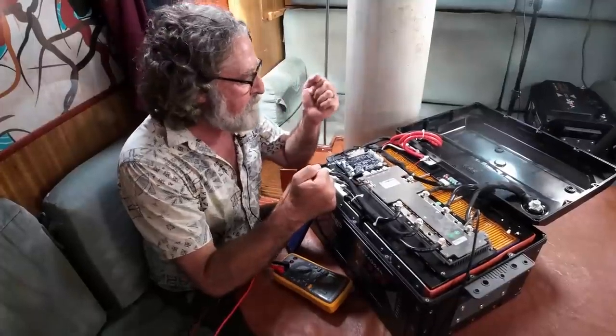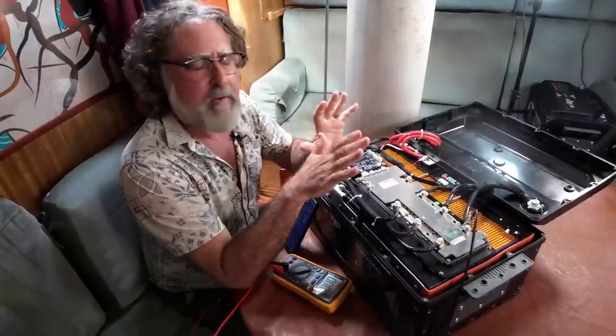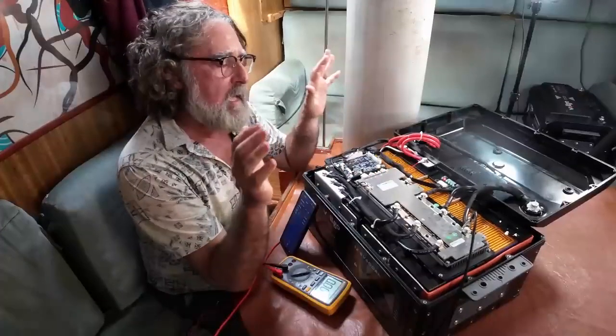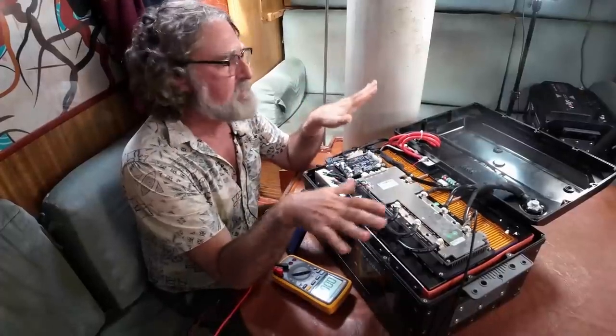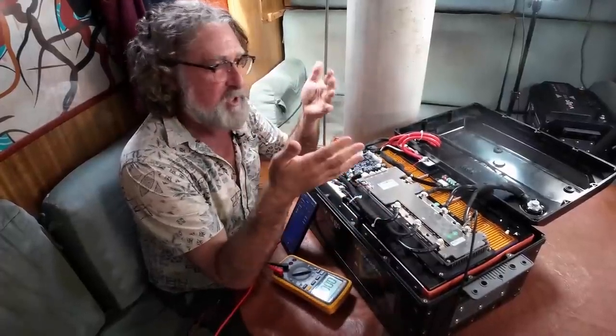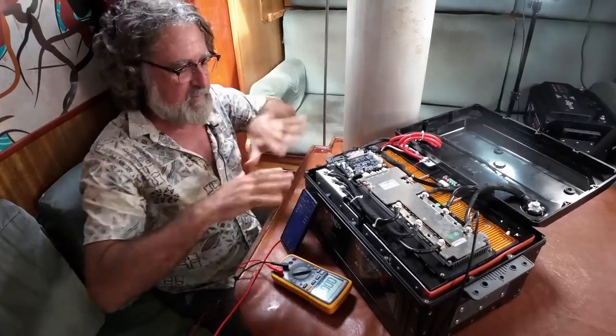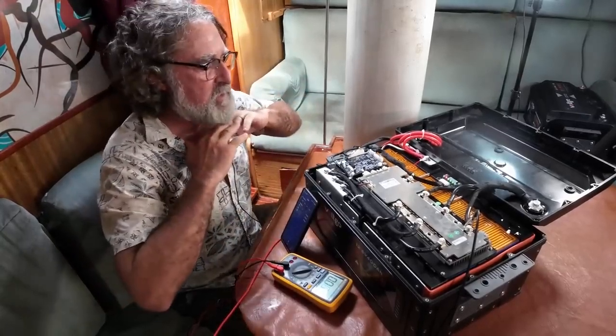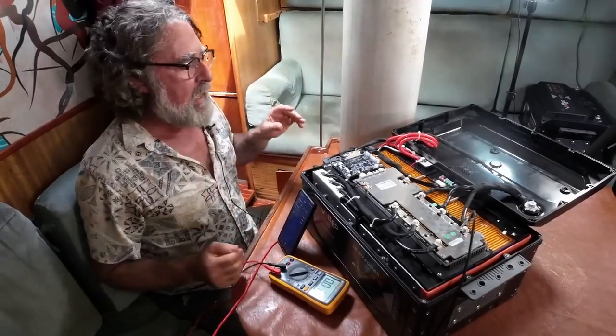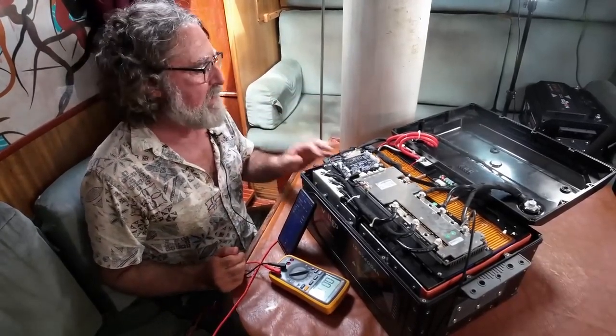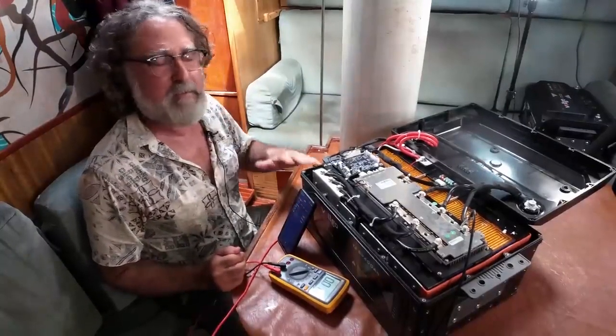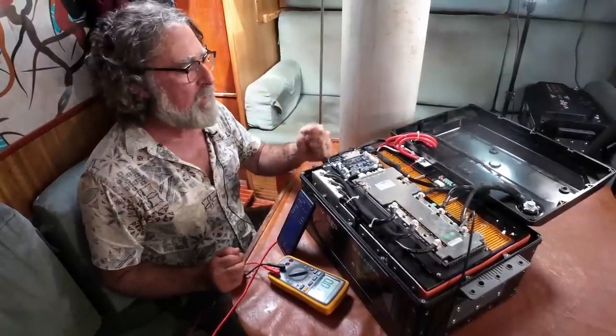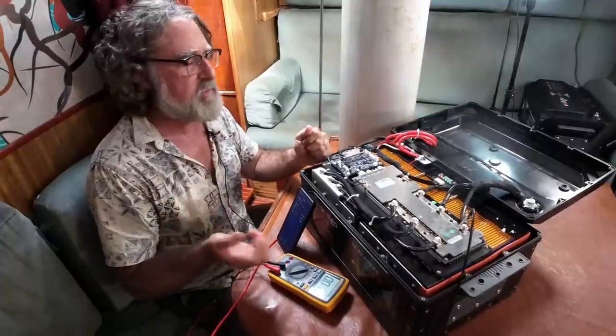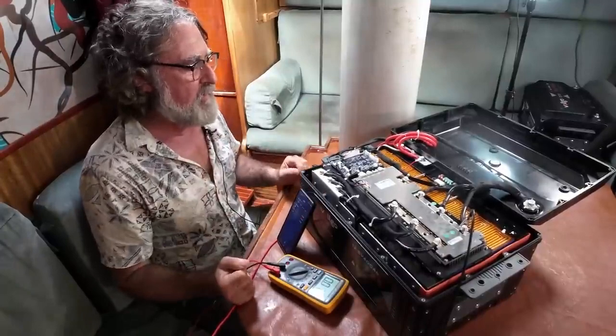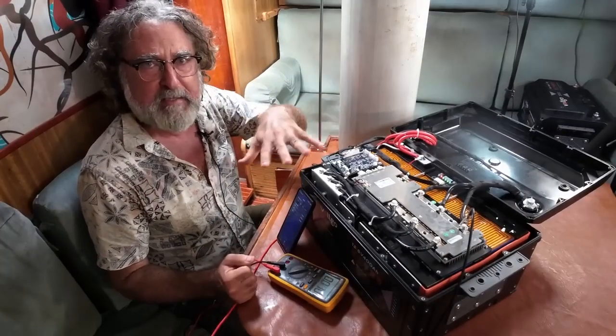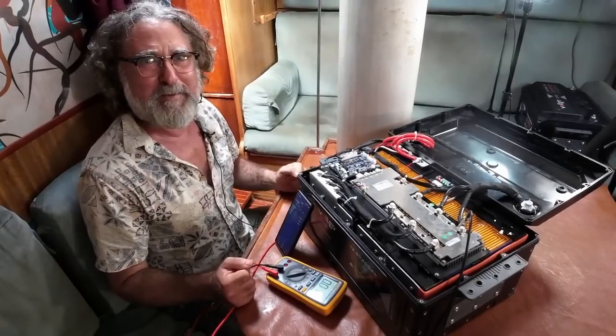Now what we're going to do is discharge it hard. I'll discharge it at 200 amps, and we will look at it with a thermal camera and see what gets hot. Then I'm going to recharge it with the bank manager, to 100%, none of this crazy high voltage stuff, just until it's at full. Then I'm going to run it through a discharge cycle, and I'll probably have a different shirt by then, because that will literally take days with my equipment. But we'll run it through a calibrated discharge source, and when we're done, we will have an answer to how many amp hours this was able to give us. And then we will talk about whether it's a good battery or not.